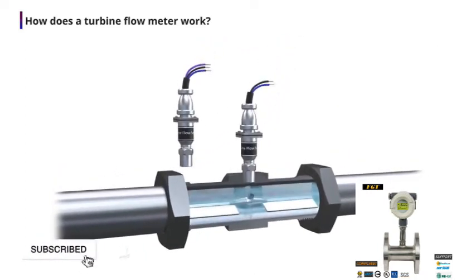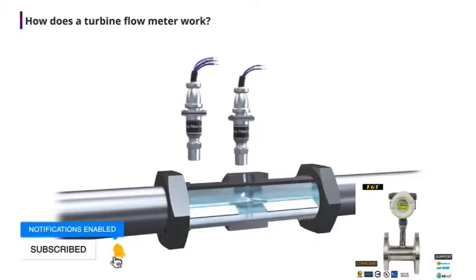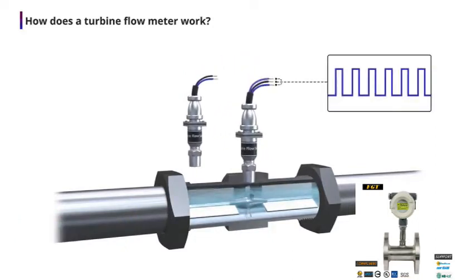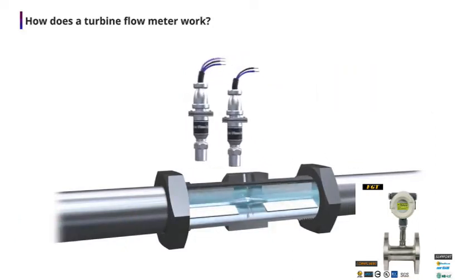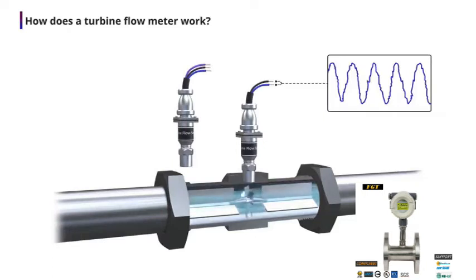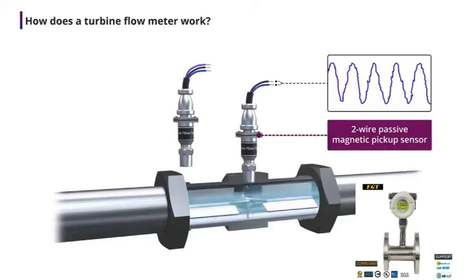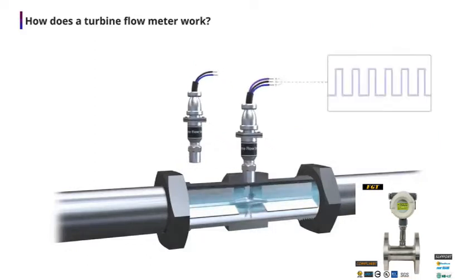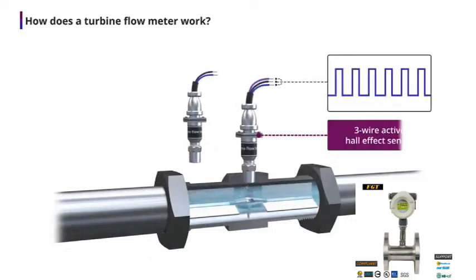The shape and the voltage level of the generated pulses depend entirely upon the type of pickup unit used. The electrical pickup sensing device could be a simple 2-wire passive magnetic pickup producing an AC type output. The electrical pickup sensing device could be a 3-wire active device, such as a Hall effect sensor, that produces cleaner and more uniform square wave pulses.